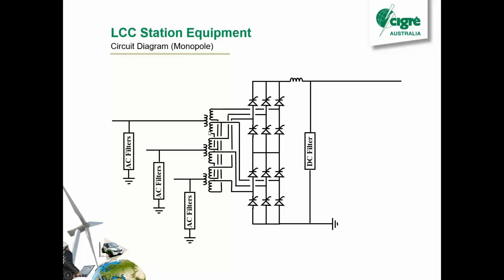They're absolutely key to give you that phase shift you need for the 12 pulse, or for one of the 6 pulse converters, but then also to give you that leakage reactance for the overlap angle. You need to have that, so the transformer does that for you. Then you have the smoothing reactor on the top. So this is to help with that DC current to smooth it out. And this also contributes towards your minimum power limit.